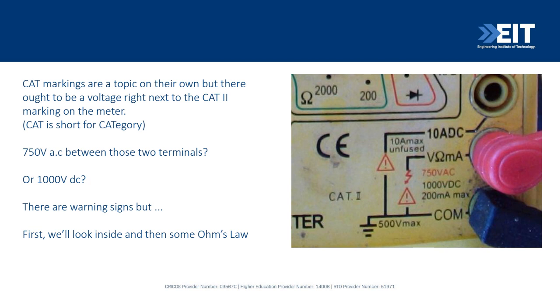But that's only once or twice. I have a different meter for doing that. 1,000 volts DC between this point and this point, I think not. Not putting 1,000 volts there. See all the sort of dirt residue that's on top of the meter? That is bad news for any sort of arcing. Now, these are recessed sockets. So the actual probe has got a plastic shroud around it, and that gives you an extra measure of protection. But would I connect 1,000 volts onto this meter? Nope, not happening.